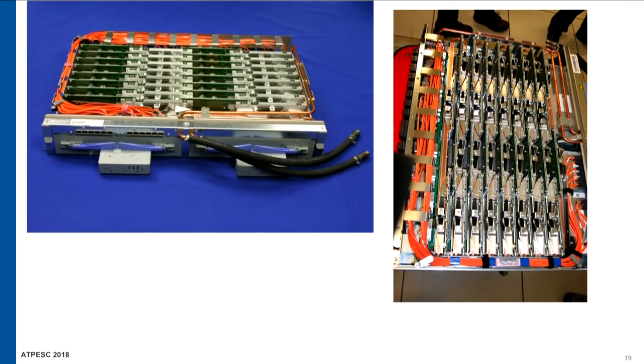If you look at this, this is one of the node boards. You can see the two hoses coming off, the supply and the return, and then a quick connect at the end. The copper runs through the rack, past the optical components first since those are most critical to cool. Then it weaves through the rack in a serpentine fashion so every processor's node board latches down onto it. There's thermal material, and the processor rests directly on the copper running through it.